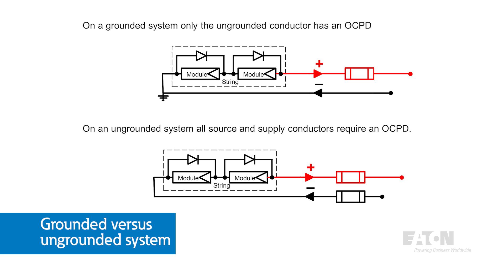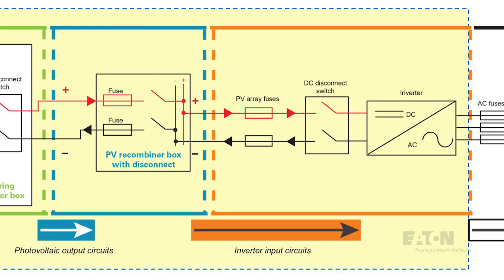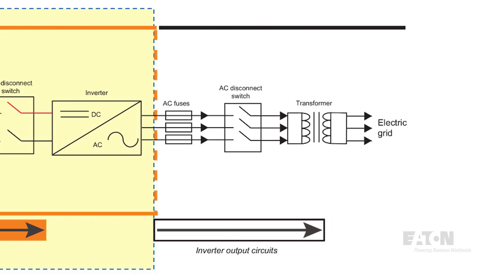In an ungrounded system, you are required to have an overcurrent protective device on both the positive and negative DC conductors. Next is the PV output circuit. Whereas the source circuit contains protection and combination for individual strings, the output circuit does so for the entire array. An overcurrent protective device is used to isolate and protect the PV output circuit conductor. If the PV system contains only one array, the output circuit and the inverter input circuit will be the same. The final combined PV output is then fed into the inverter, which converts the DC to AC. Overcurrent protective devices in this circuit protect the conductor feeding the DC side of the inverter, as well as the inverter itself. Finally, the inverter output circuits connect the PV system to the grid. This part of the system is AC, which is more familiar to designers and installers.